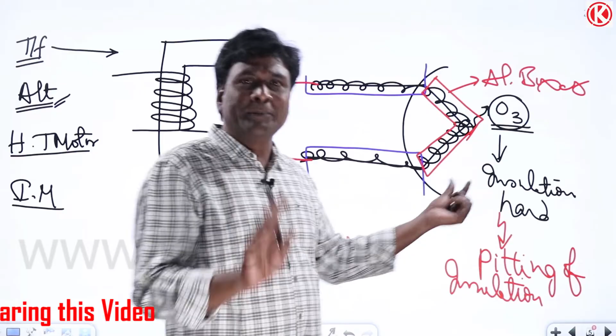Very popular, NTPC and all. Why? In order to limit pitting of insulation. Why is pitting of insulation happening? Because insulation is becoming hard and it is breaking into broken pieces. Why? Because of ozone. Why? Because of corona.